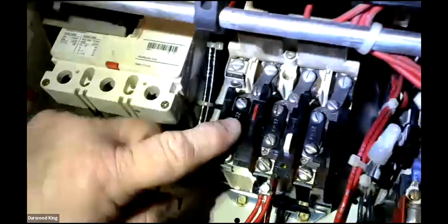Now, you see those 2 screws right there? Yep. 2 screws. These are separate fixed overloads that are not adjustable. Now, an adjustable overload is going to be this. So you're liable to run into either kind. This one here has a knob that you can adjust. You see that? Mm-hmm. This one goes from 9 amps up to 45 amps, so it can handle a wide variety of motors. Once you do your calculation we just went over, at 125% or 140%, then you dial that in for a particular motor. You've got to be careful what you do with this. If you go too high with that, you'll end up smoking some wires or probably smoking a motor. We won't.